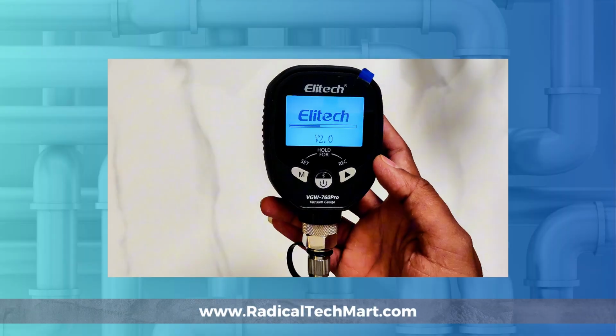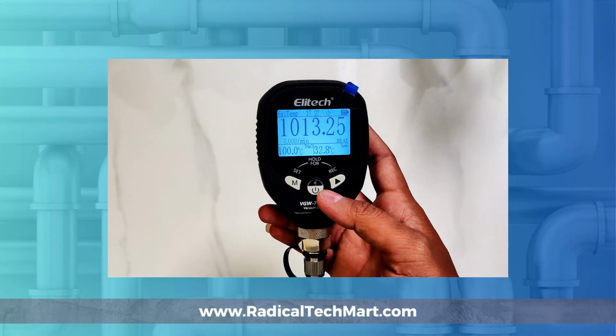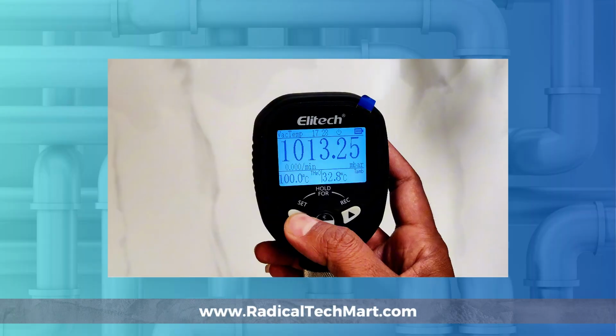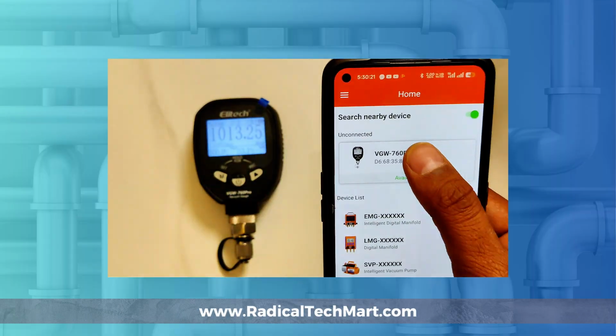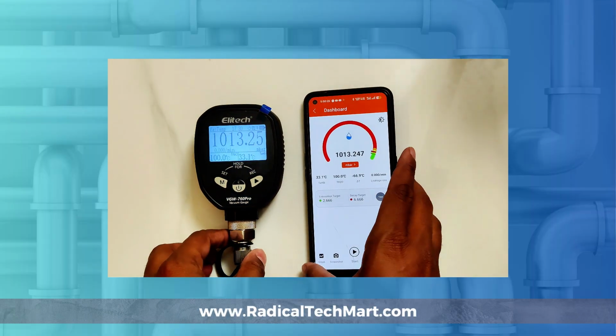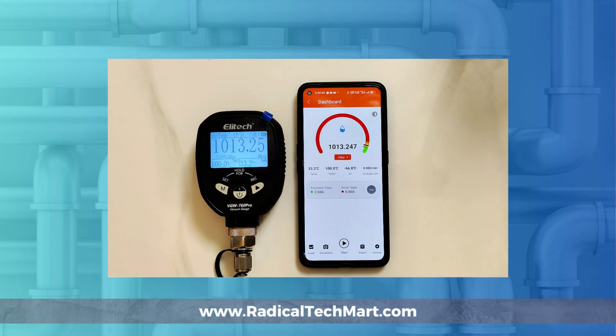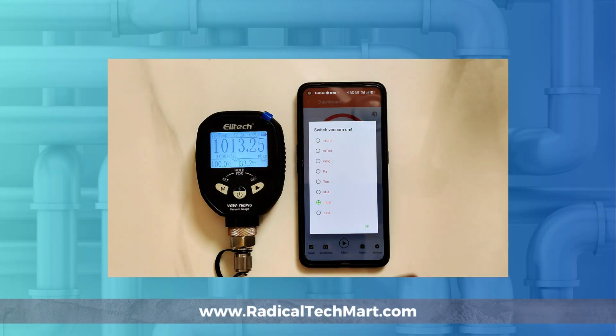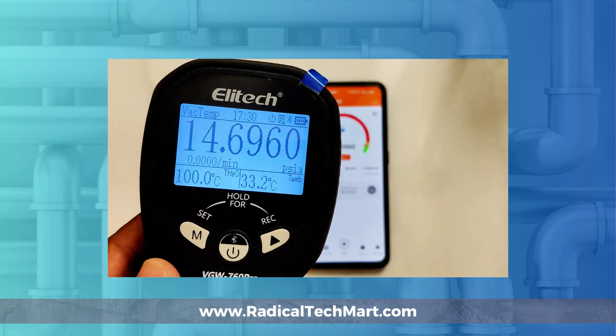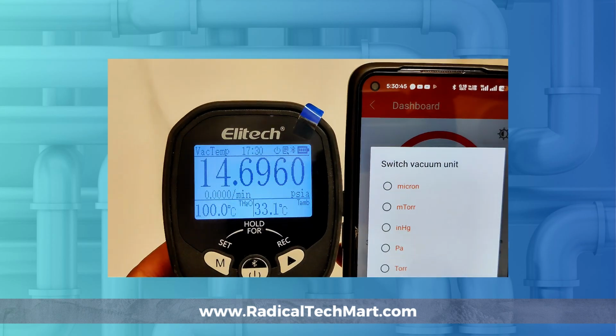Now turn on the gauge. Start the vacuum pump and monitor the reading. If needed, connect the gauge with the Elitech Tools app for wireless monitoring. You can also start data recording if you need service records. One important point: before turning off the vacuum pump, close the valve and isolate the pump from the system. This helps protect the gauge and system.